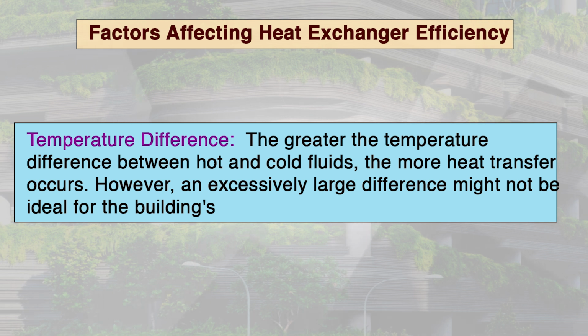However, there is a caveat: an excessively large temperature difference might not be ideal for the building's needs. For example, if the incoming fresh air is preheated too much in winter, it might require additional cooling to reach a comfortable temperature, negating some of the energy savings.